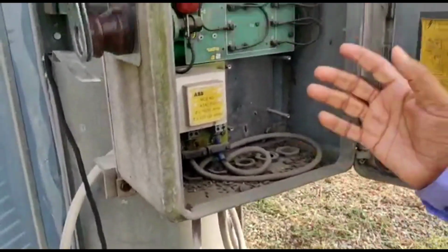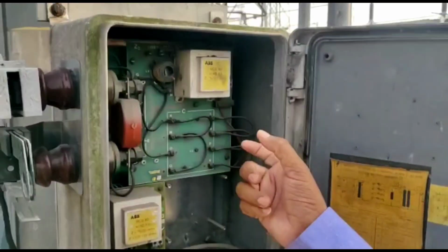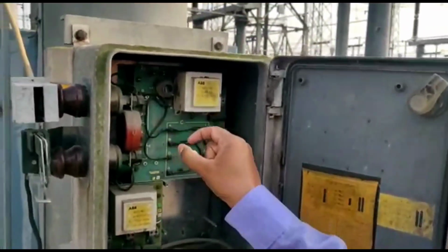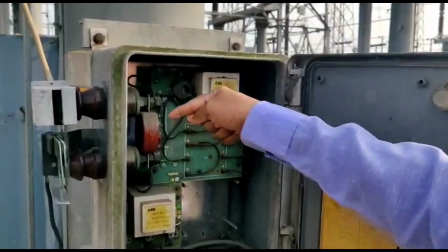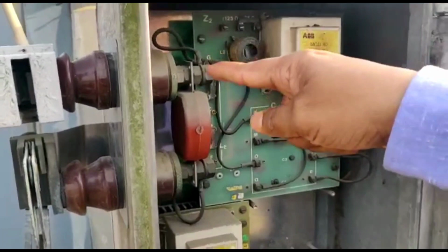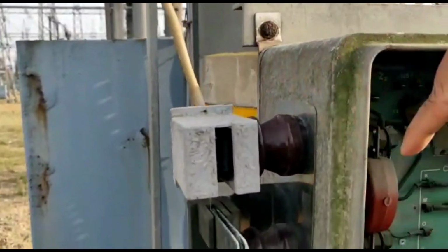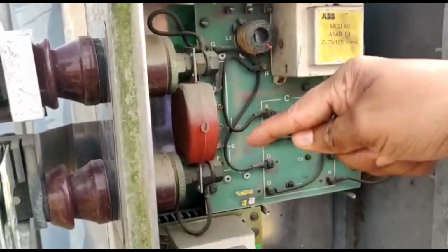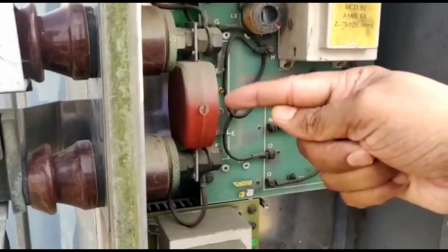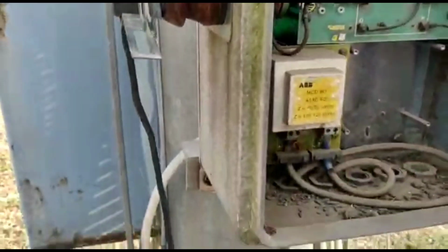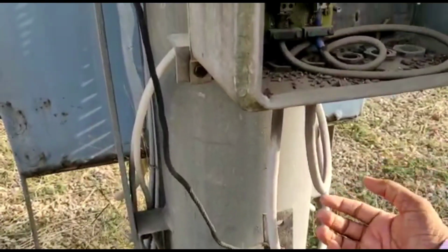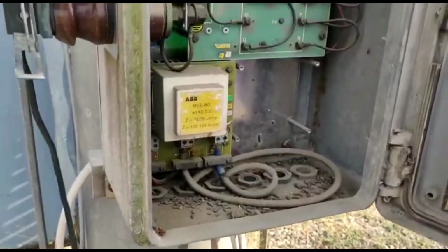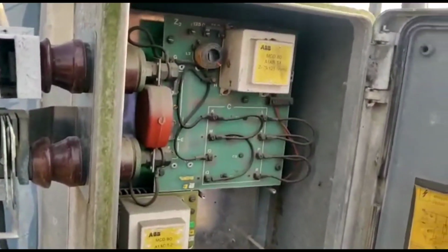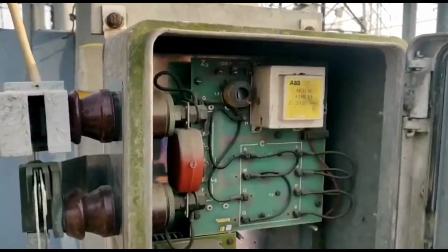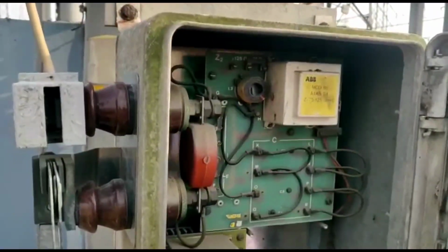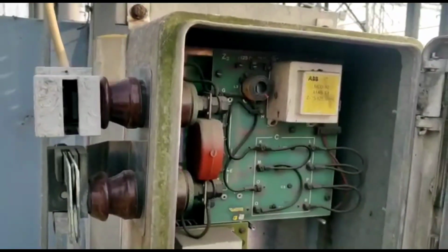to the control room. And it also has a surge unit or surge protection unit, and whenever there is a high voltage, this surge protection unit will operate, and when it operates, it will create a short circuit here, and this short circuit path is connected directly to ground. So if there is any high voltage signal, that high voltage will lead to operation of this, and this then connects to ground. That means no high voltage signals will be transferred to your PLCC equipment in case of any over voltages, and your PLCC system will be saved, or will be in better shape to mitigate any chances of damage due to over voltages in the transmission line.